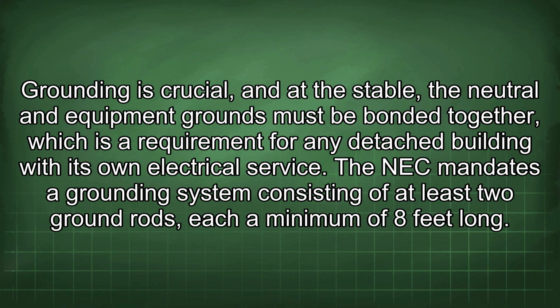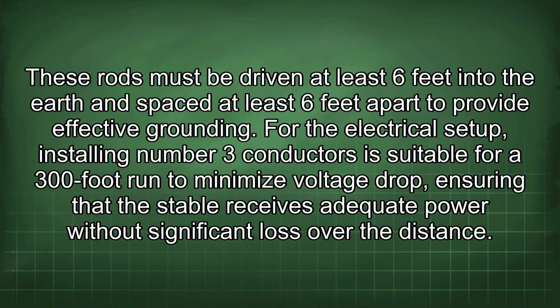The NEC mandates a grounding system consisting of at least 2 ground rods, each a minimum of 8 feet long. These rods must be driven at least 6 feet into the earth and spaced at least 6 feet apart to provide effective grounding. For the electrical setup, installing number 3 conductors is suitable for a 300-foot run to minimize voltage drop, ensuring that the stable receives adequate power without significant loss over the distance.